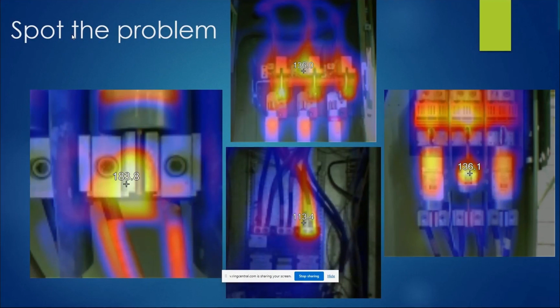And the one on the right is a fuse mismatch. Fuse mismatches are a big problem. When we open up these panels, they usually show an imbalance and generate heat signatures that show a problem. That's exactly what happened here. They used two different classifications of fuses. They were not matched at all. The recommendation there is, of course, to replace all three fuses, then rescan.